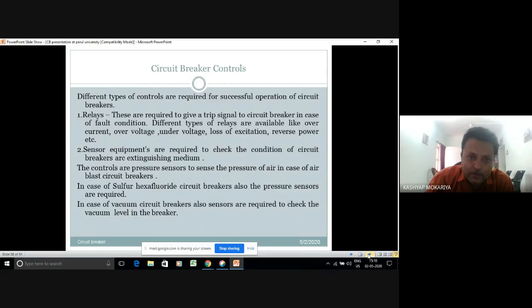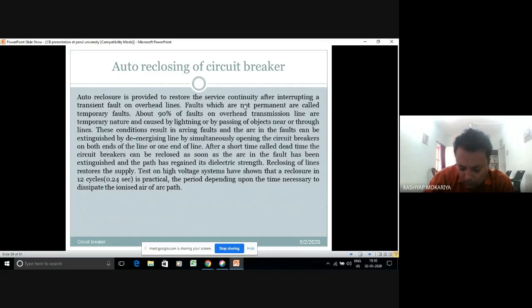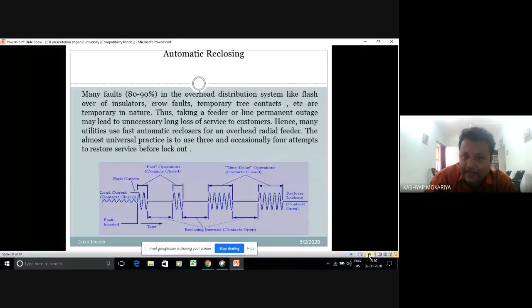So that is the important part. Auto reclosing. Auto reclosing is provided to restore the service continuity after a transient fault, which is not permanent. I'll call it a transient fault, that I have already explained. Reclosing of lines restores the supply. Test on high voltage system have shown that the recloser in 12 cycles is practical. It will vary as per the standards.